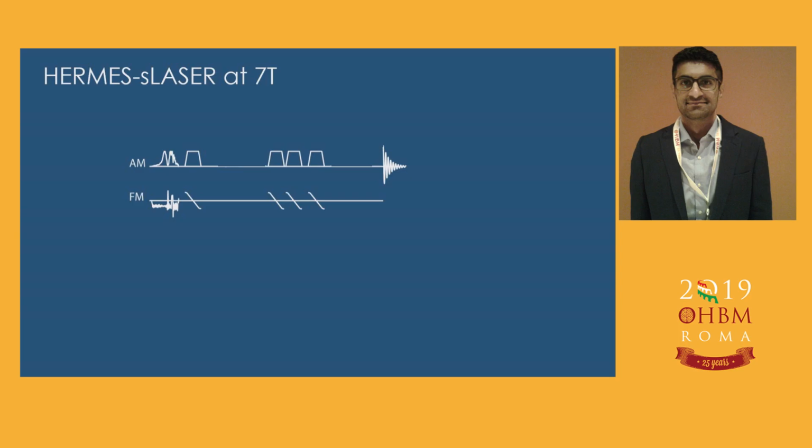So several studies conduct single voxel spectroscopy using the semi-LASER sequence. And how do you get that sequence? You start with the slice selective excitation pulse with frequency modulation, and use adiabatic pulses, which are also slice selective, with frequency modulation. This is where the benefit comes in. This sequence implements adiabatic pulses. They are known to have higher bandwidth, so they reduce your chemical shift displacement error and increase your editing efficiency, but they're also less sensitive to B1 inhomogeneity. So you need to reach a certain threshold, and after that, if it varies, it doesn't matter, because it just requires that minimum amount of B1 to work optimally.